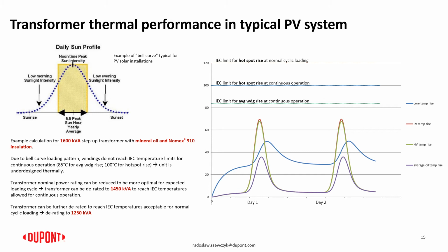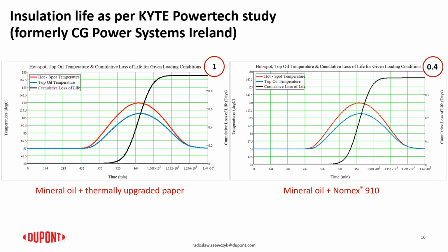And if we consider that this peak load, or the peak temperature for a short duration of time during the day, is the design factor, then the transformer design could be optimized if the insulation system would allow higher temperatures than conventional transformers. This is part of the study that was done by the KYTE Powertech in Ireland.